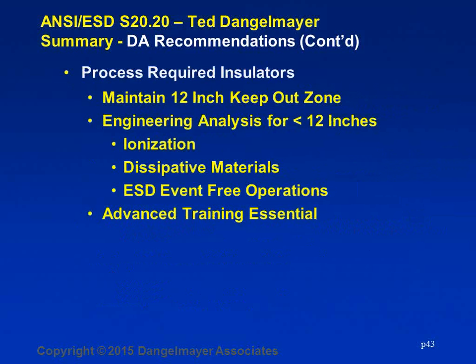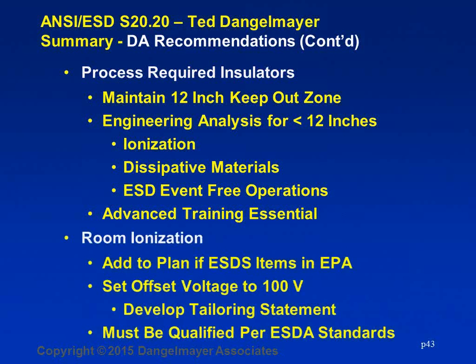Process insulators, the bottom line is we recommend keeping a keep-out zone of a foot, that is workable, manageable, and anything closer than that, you need to do an engineering analysis to see what is the most technically and cost-effective remedy. And the bottom line there is you may need advanced training for that.